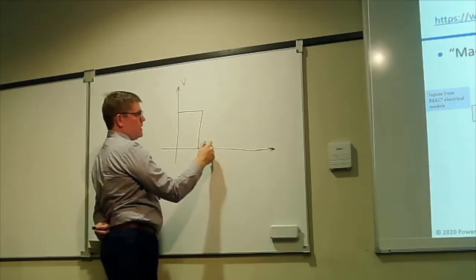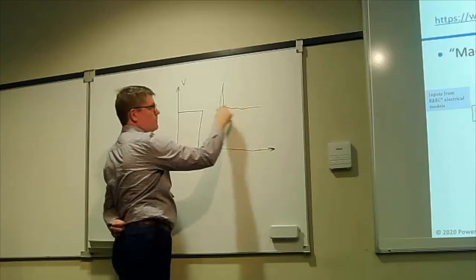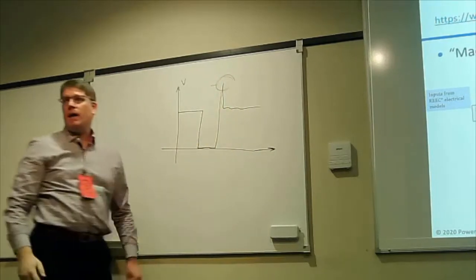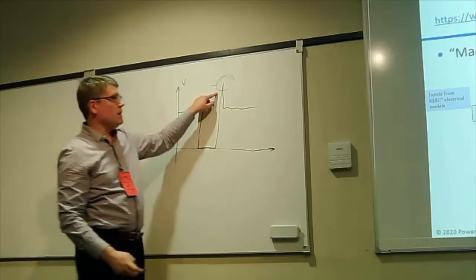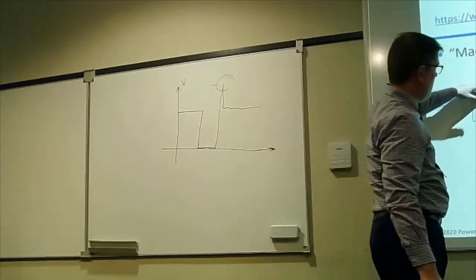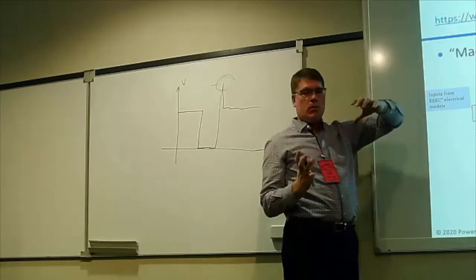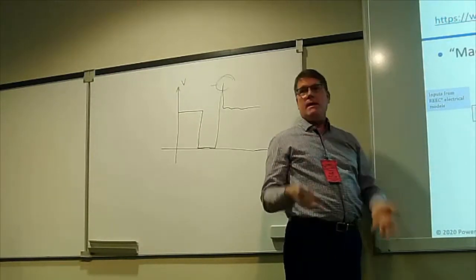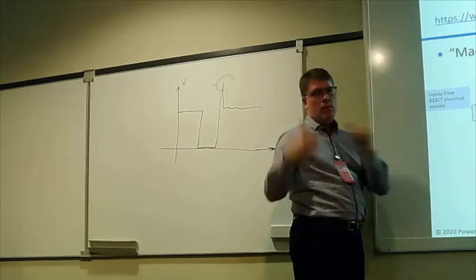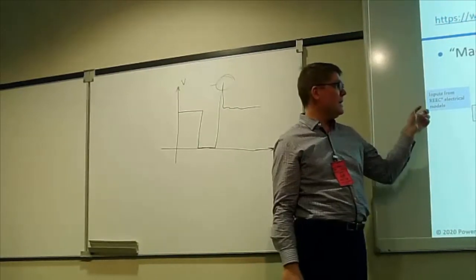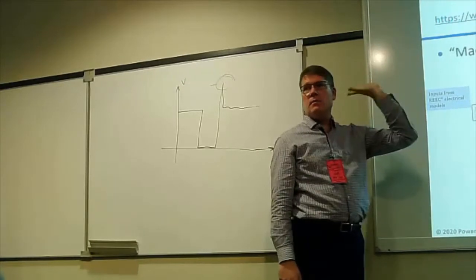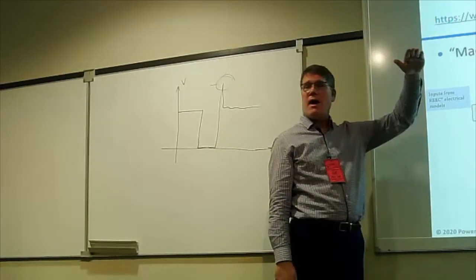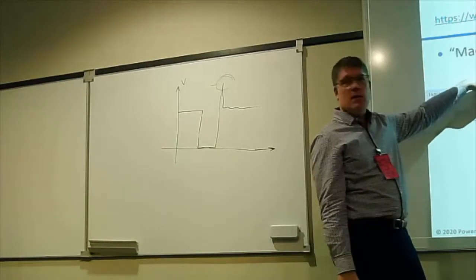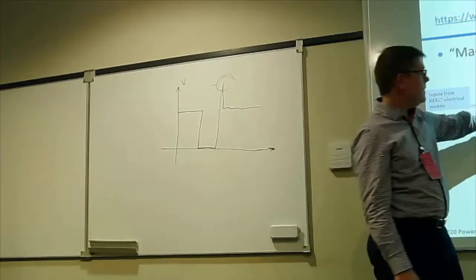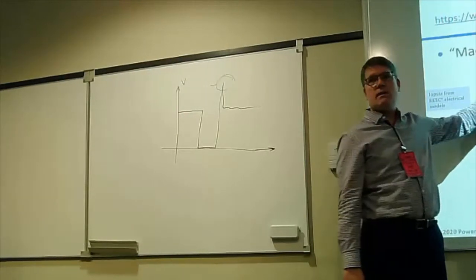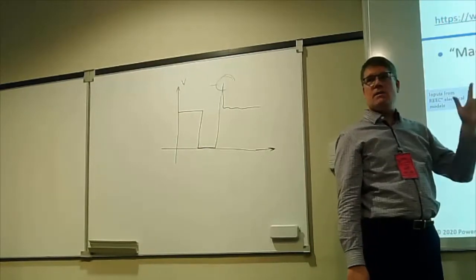A fault happens, it goes down, and you always get these spikes. This spike here, and that spike can go quite high. That spike is occurring because I have a fault occur. The control system is going to look at that fault and go, oh, I need to pull the voltage up. So if you go look at the renewable model, the electrical control, we'll look at it in a second, it's going to push that up to the maximum desired reactive current, the maximum possible reactive current. And it's going to be sitting right there.